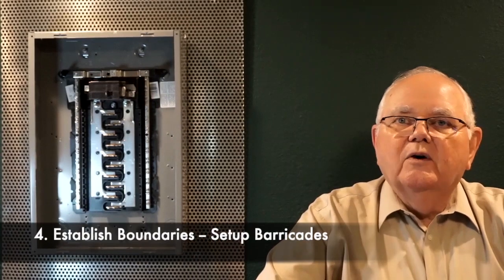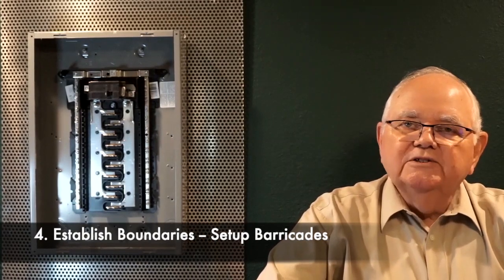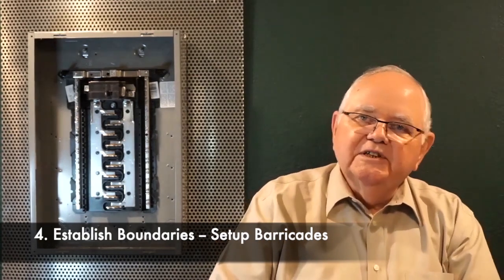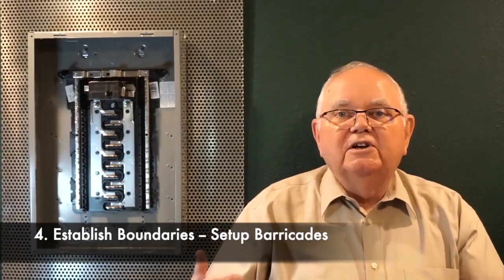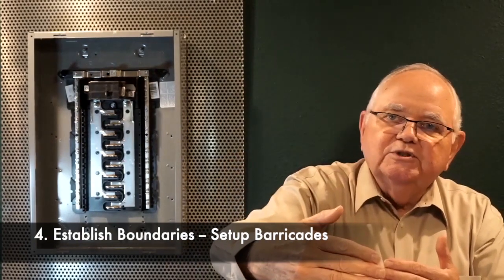Then if the equipment looks good and we're ready to work, we want to set up our boundaries and go to work. So we set up barricades is what we do. So we look on our arc flash label once again, and we see what is the greater distance, either the limited approach boundary, which is based on shock protection, or the arc flash boundary, which is based on burn protection. Well, I don't want anybody else to get burned around here, and I don't want anybody else to get shocked. So I'm going to set up a physical barricade, red tape, gates, the expanding gates, whatever it is I use. And I'm going to set it at either the limited approach boundary or the arc flash boundary, whichever one is greater. That way, nobody gets injured anywhere around me.